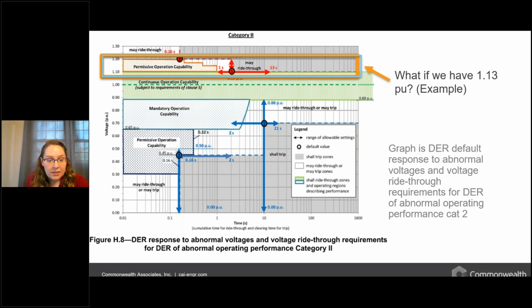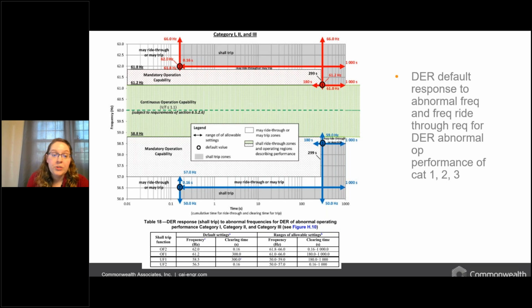A battery system, which we could think of as including the inverter to get us onto the AC grid, a controller, things like that, and all DERs, in fact, that are interconnecting need to be designed to accommodate this. We also have a similar consideration for frequency in IEEE 1547. So here we see yet another chart where we have lots of colors and different options to trip or not to trip. But this is below the level of detail for our discussion today. But it's just to give you an idea of how IEEE 1547 is serving as a standard that could influence our design of our battery systems.